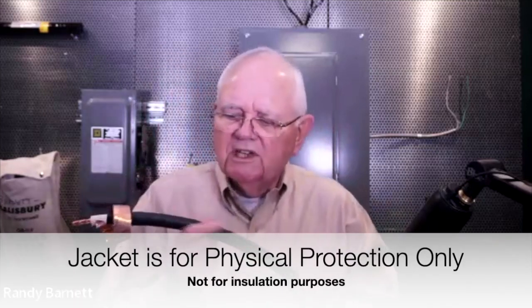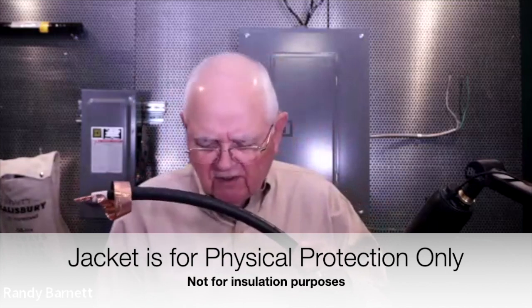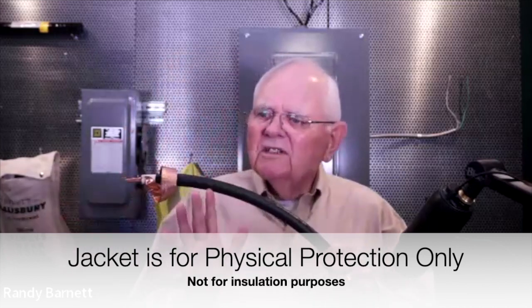And 90 degrees C, that's 194 Fahrenheit. That's pretty warm. It's either a thermoplastic or a thermoset insulation, and we already said it's a thermoset insulation. And it has a jacket or a sheath or an armor. Well, this has a plastic type jacket over the outside of it. So maximum operating temperature on this cable conductor is 194 degrees Fahrenheit, 90 degrees C. If that's not good enough, if I need a higher temperature application, I can go up to MV105 according to the table. MV105 is good for 221 degrees Fahrenheit, 105 degrees Celsius. So it just depends on your application.